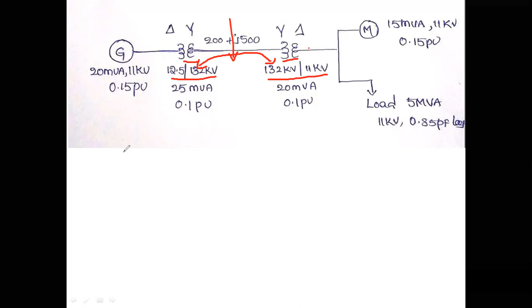So instead of 11 kV, now I am going to consider the base kV as 12.5 kV. Why? Because if you are considering 12.5 kV, you need not convert the ratings of all the sections. Suppose you are choosing 11 kV as the base value, now what is the corresponding secondary voltage? So the first conversion is at this point. Similarly, for the same voltage, what is the secondary voltage of this one? So secondary transformation. The third one is this one, and the fourth one is this one. If you choose 11 kV as the base value, you have these conversions. Suppose I am choosing 12.5, obviously you need not convert this one, and again you need not convert this one. If this is not changed, obviously this is also not going to be changed. Why? Because 11 kV is the operating voltage of the motor section as well as the load section. Okay, so that will give you less number of conversions if we choose 12.5 kV as the base value, right?